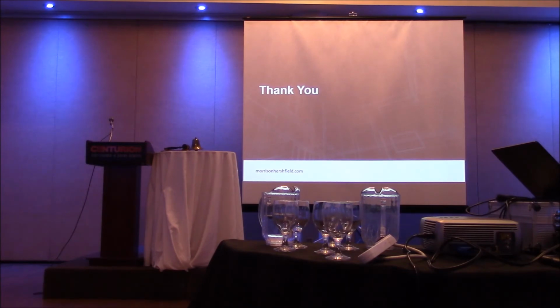One of the things I love to do personally in similar situations is to see if I can get that transformer outside. Feed the transformer, but put it as a pad mount transformer outside adjacent to the building, so I don't have to get feeders out of the building. I'm not using floor space in the building, but still keeping it close because the cables are going to get much bigger at 600 volts. Yeah, the transformer at almost 10 to 1, it's huge, right? But conversely, the opposite question, if there's a 600 volt chiller and it's of the size where a 4,000 volt chiller is available, is it really beneficial to go to the 4,000 volt chiller?